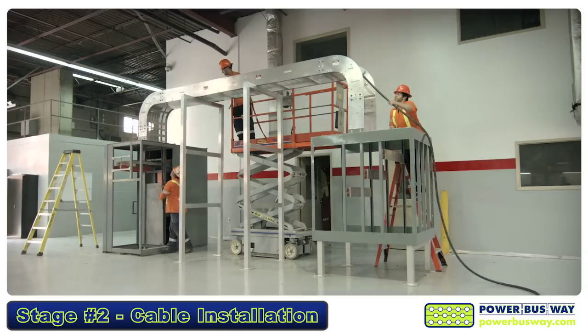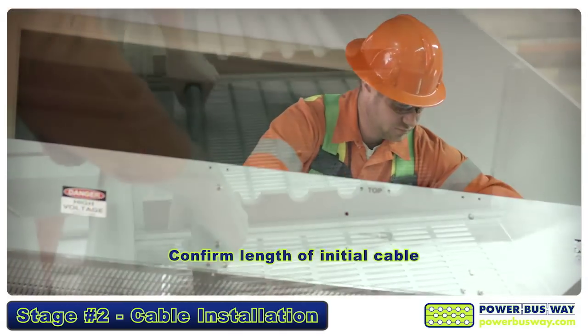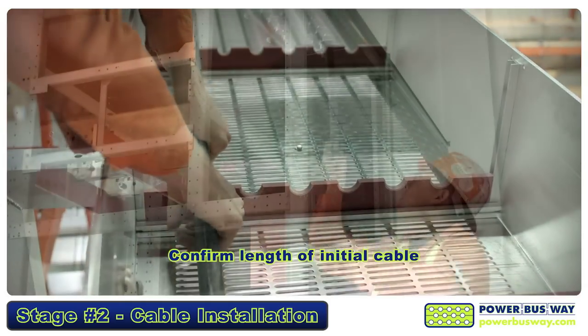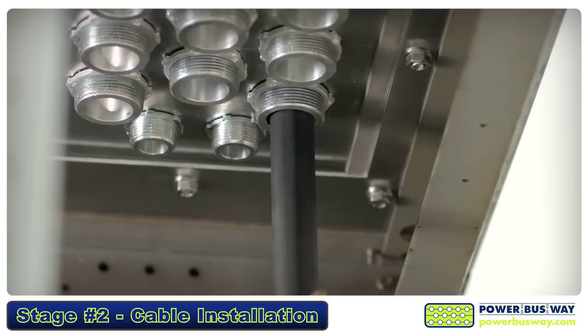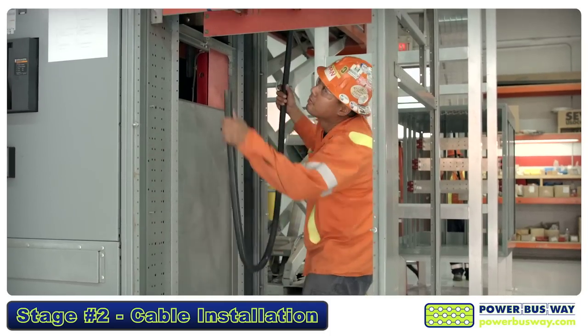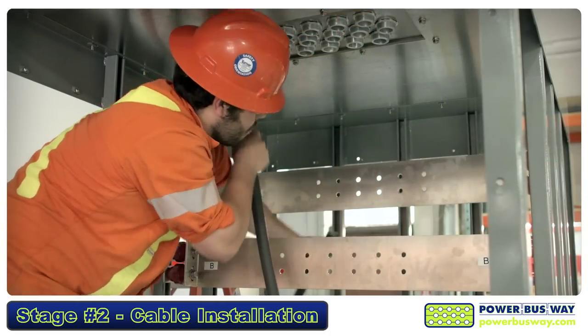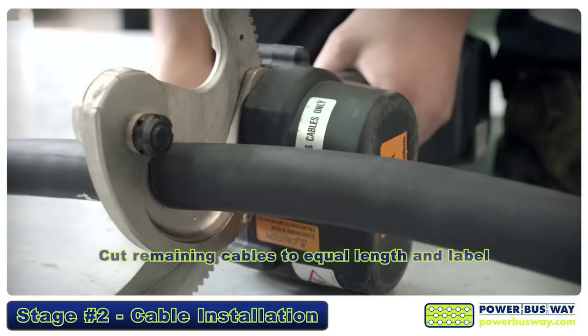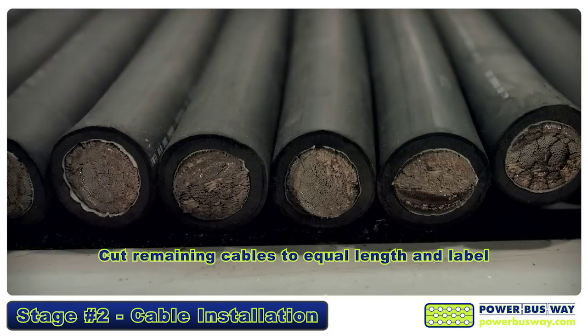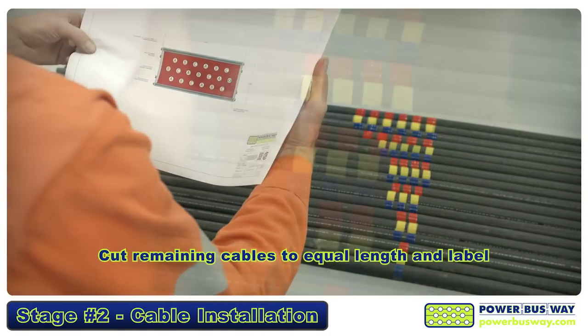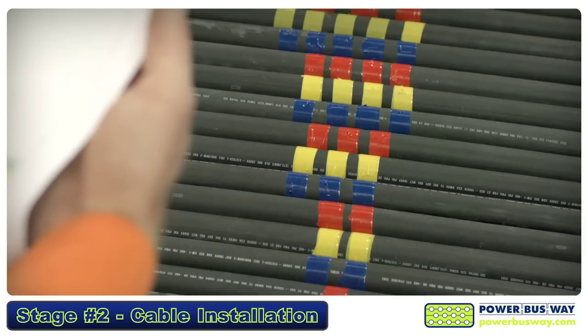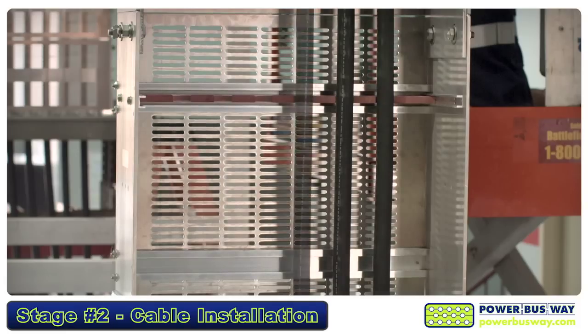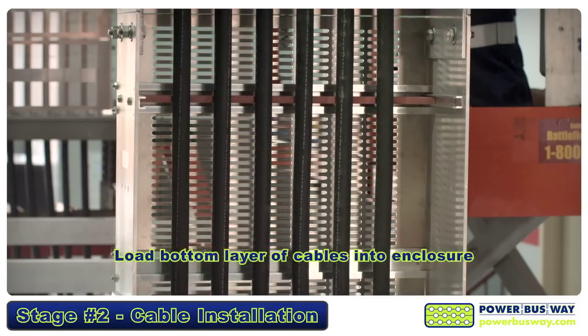As the length of all other cables will be based on the initial cable, it is critical to confirm that the length is correct. Install the initial cable into the enclosure and pull into position, eliminating any slack, leaving adequate tail length for the terminations. Satisfied that your initial cable length is correct, cut the remaining cables, ensuring that they are all of equal length. Remember to label each cable individually for the correct phase arrangement as outlined in your manual and diagrams. Next, load the bottom layer of cables into the enclosure, tightening each watertight connector one at a time prior to placing the next cable.